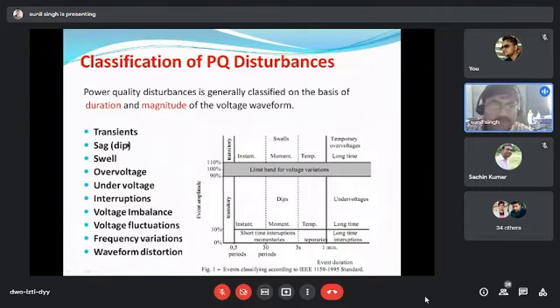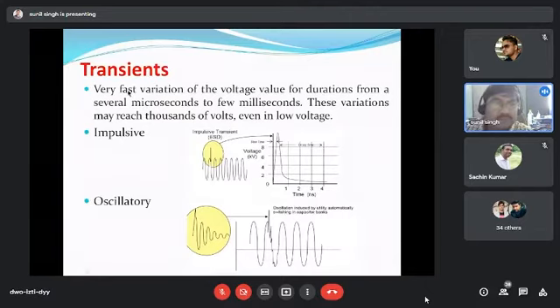So most of the power quality disturbances, transient, sag, swell, over voltage, under voltage, and interruptions, can be defined from this curve, and it is a very important curve given by the IEEE 1159-1995. So if we come to the transient, it may be an impulsive transient or an oscillatory transient. Most participants are from academics, so it is very important to know about the transient. It is the variation of the voltage, a very high voltage for a very short duration, known as the transient. It may be impulsive or oscillatory.